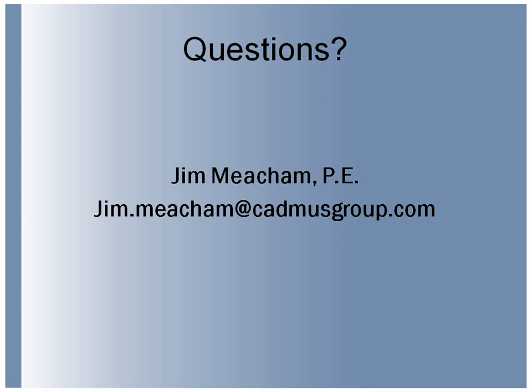I'll quickly add a related issue on economizers. NBI was involved in an eye-opening and somewhat famous study that suggested 75% of economizers did not work as designed within 5 years of installation, including ones that were just installed. We were involved in technical committees with manufacturers on this for a while, and at one point one of the major manufacturers of economizer controls admitted their controller had never worked - they knew it didn't work, and even the way it was designed, it never could have worked that way. It wasn't designed for that, yet it had been used as the main controller for years. They announced this when they finally came out with one that actually did work.